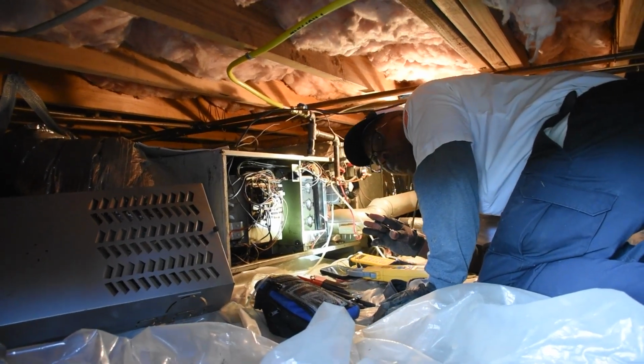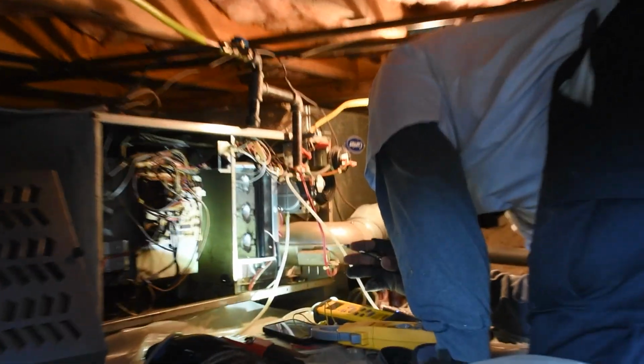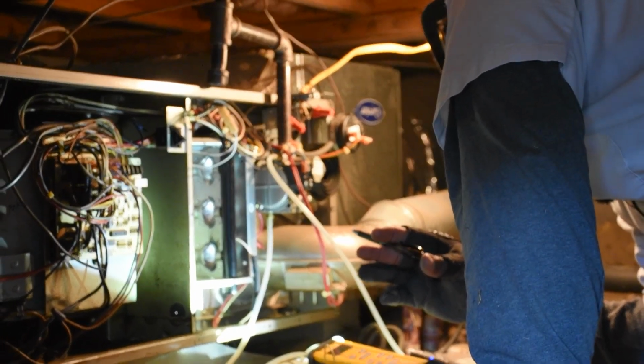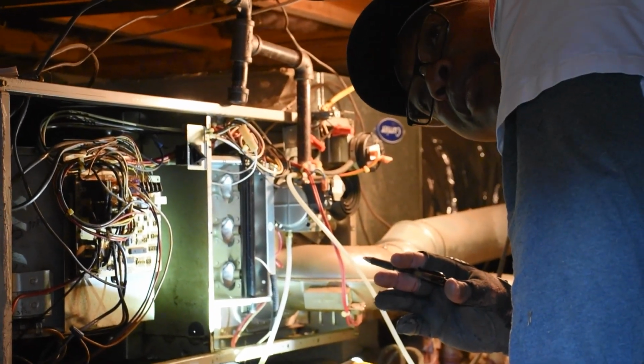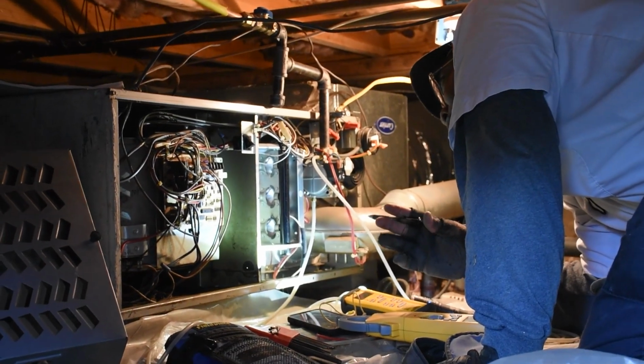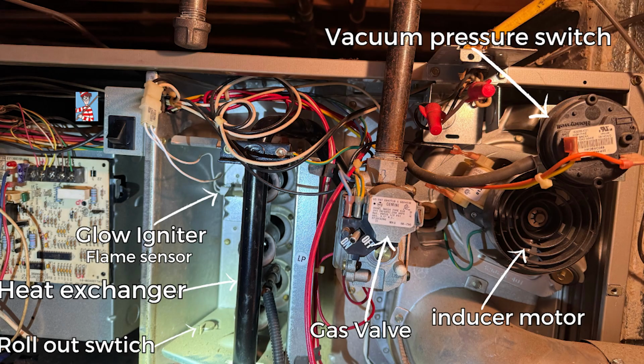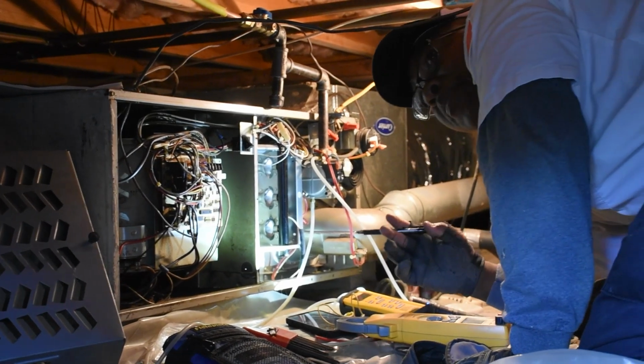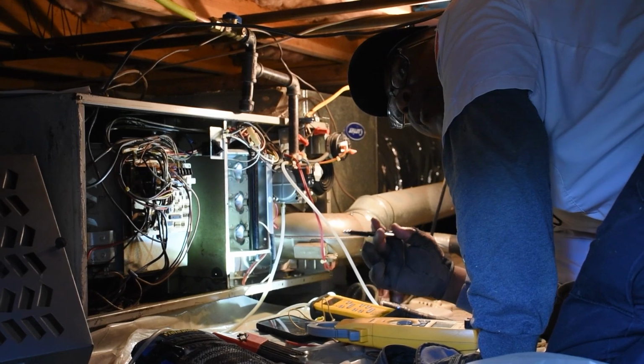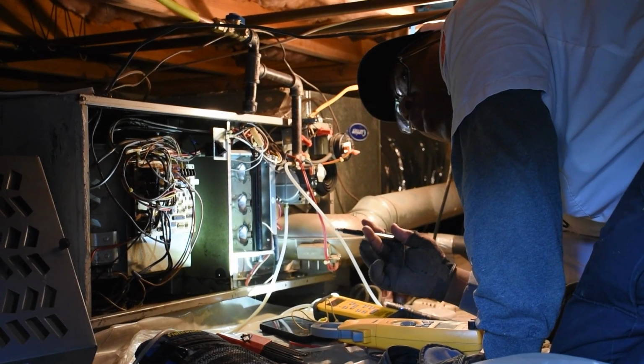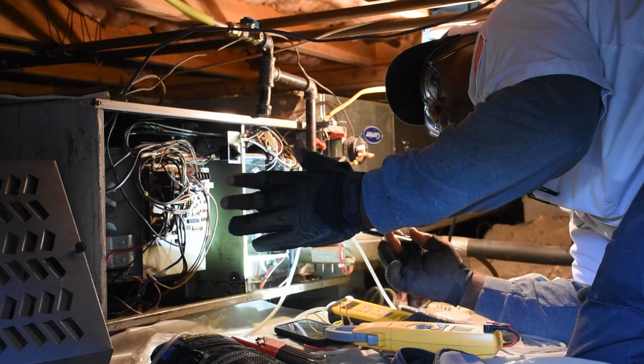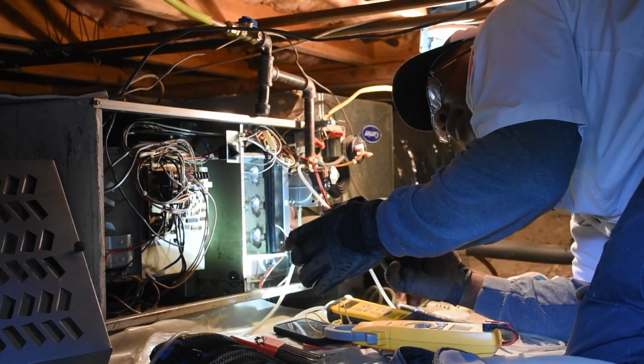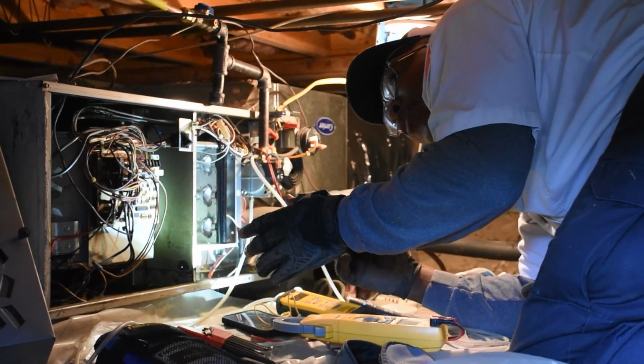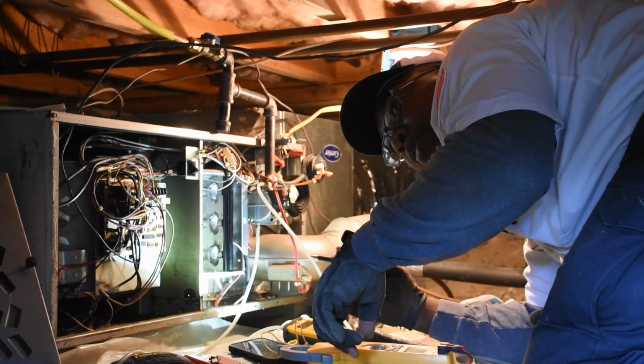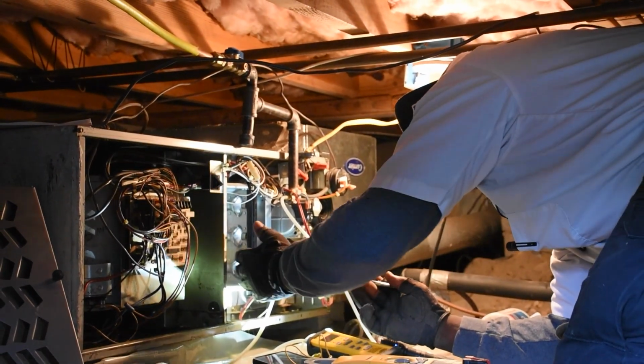Now there are a few other components that play a part. I would say they operate in the background, but they're there for safety, which is called the rollout switch. The rollout switch is always placed just outside of the burners. Now, should there be a crack, a rust, or a break in the heat exchanger, once the blower motor is pushing that air across the heat exchanger, it would create a pathway for that airflow to go into the heat exchanger and push the flame out.